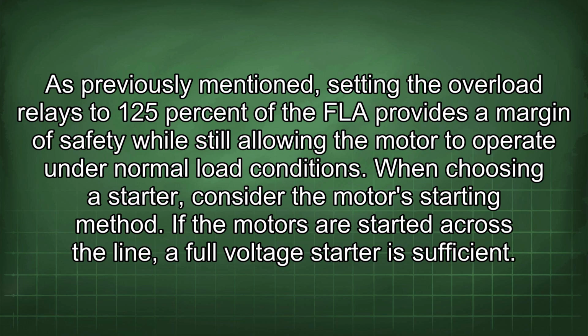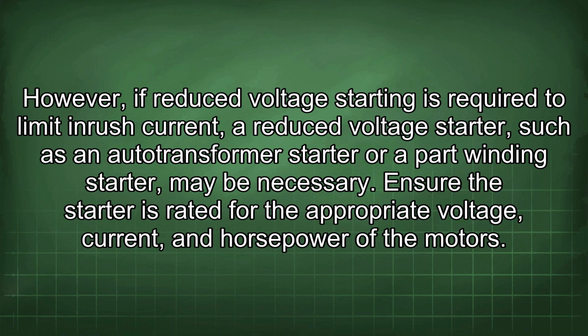When choosing a starter, consider the motor's starting method. If the motors are started across the line, a full voltage starter is sufficient. However, if reduced voltage starting is required to limit inrush current, a reduced voltage starter, such as an auto-transformer starter or a part winding starter, may be necessary. Ensure the starter is rated for the appropriate voltage, current, and horsepower of the motors.